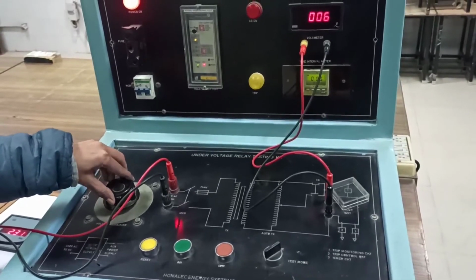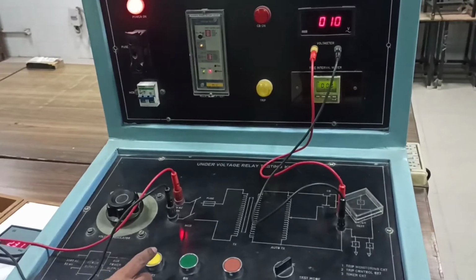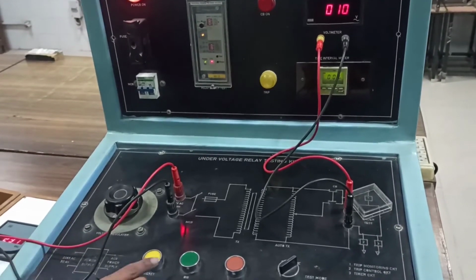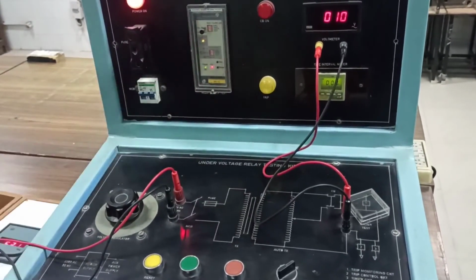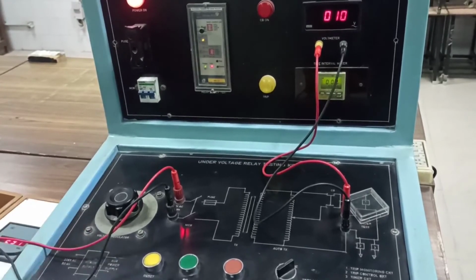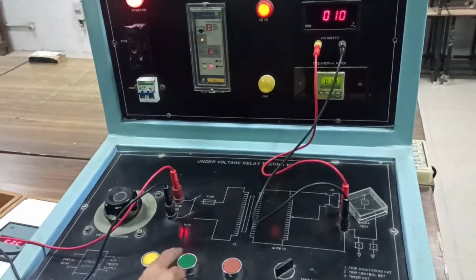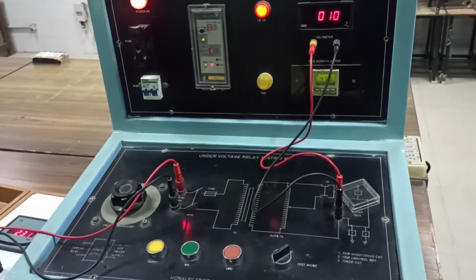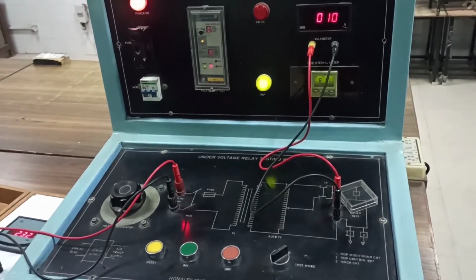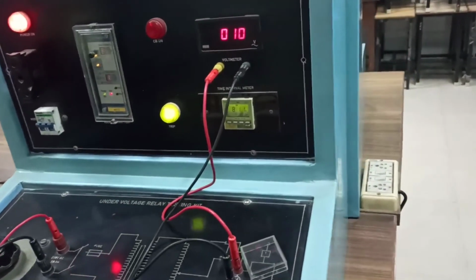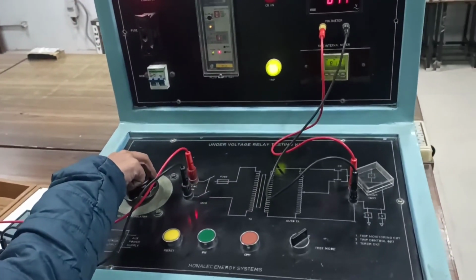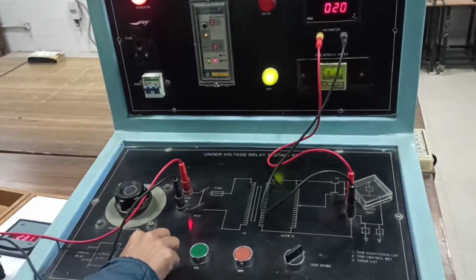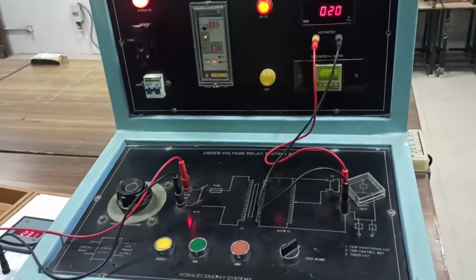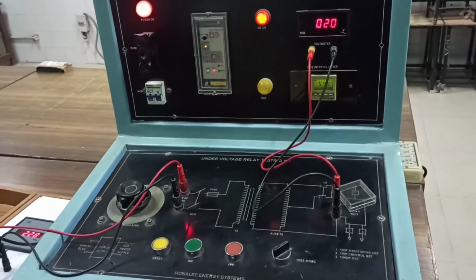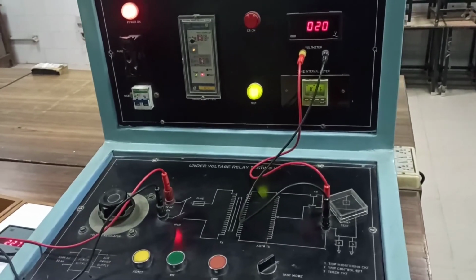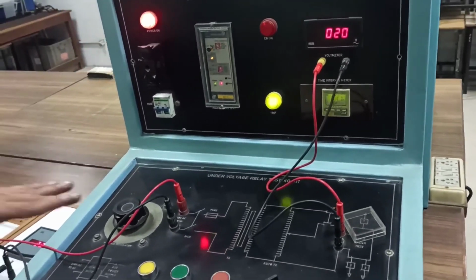Increase the voltage to 10 volt. In this kit you increase the voltage at intervals of 10 volt up to 90 volt, because the reference voltage set here is 95 volt. Above 95 volt the relay is not tripping. Again switch on. Now at 10 volt the trip time is 8.11 seconds. At 20 volt, it is 8.17 seconds. As you increase the voltage, the trip time also increases.